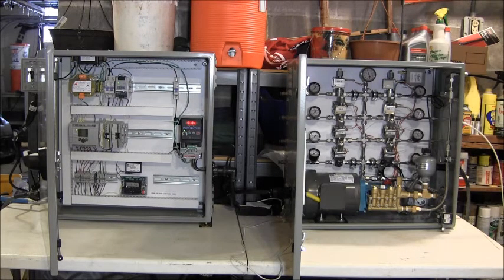There is one other control that I haven't put in yet. I do need the proper fitting to put it in, but over here in the lower right-hand corner is a flow meter itself. And that is going to go in the line right above it there, right just below the incoming pressure sensor. There is a piece of tube there. That's where that flow meter is going to go. It'll monitor the amount of water that's coming into the unit and be able to log how much water, or how much capacity, the unit is actually putting out.